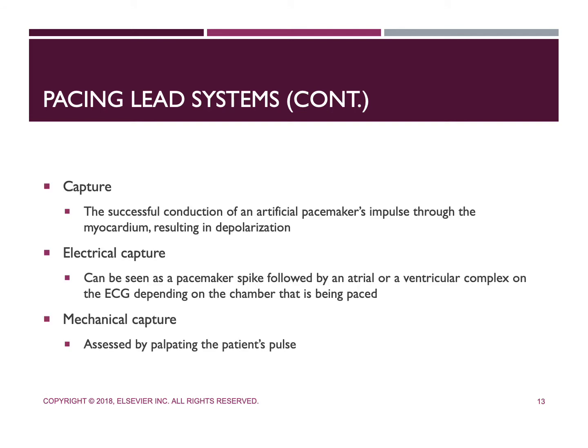Capture is the successful conduction of an artificial pacemaker impulse through the myocardium, resulting in depolarization. Capture is obtained after the pacemaker electrode is properly positioned in the heart. With 1-to-1 capture, each pacing stimulus results in depolarization of the appropriate chamber. On the ECG, evidence of the electrical capture can be seen as a pacemaker spike followed by an atrial or a ventricle complex. Depending on the cardiac chamber that is being paced, mechanical capture is assessed by palpating the patient's pulse or by observing right atrial pressure, left atrial pressure, or pulmonary artery or arterial pressure waveforms.